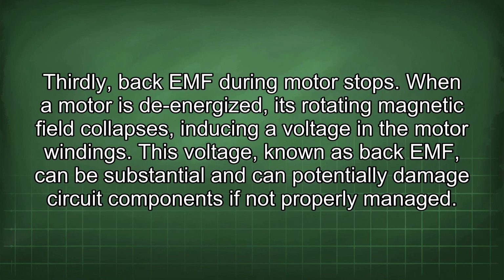Thirdly, back EMF during motor stops. When a motor is de-energized, its rotating magnetic field collapses, inducing a voltage in the motor windings. This voltage, known as back EMF, can be substantial and can potentially damage circuit components if not properly managed.